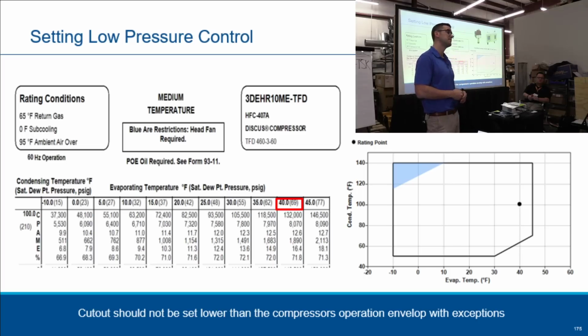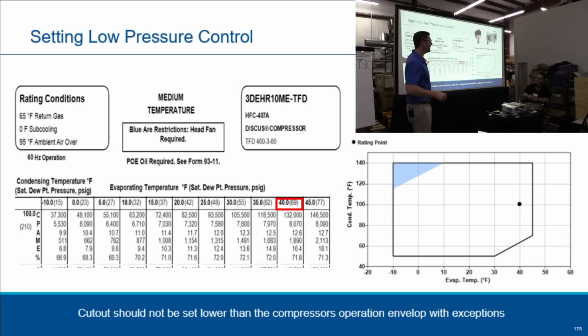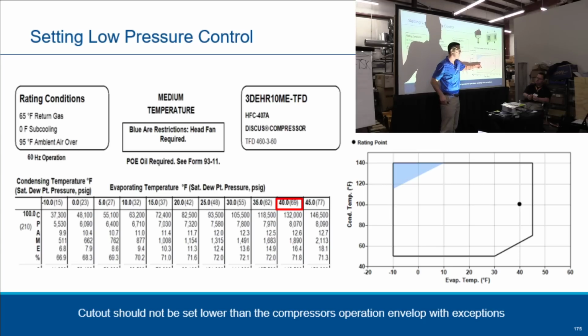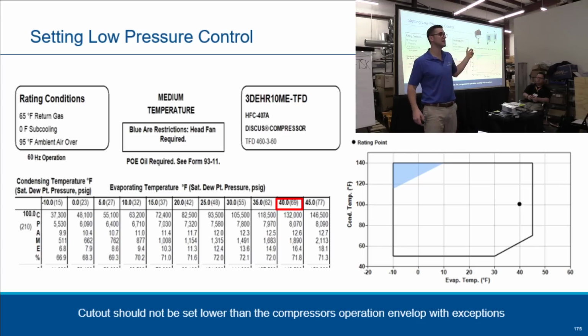Okay. So does everybody kind of understand this? If you set it, instead of all the way down to here, only right to here, just say 0, you're doing less work on that compressor, right? So a good mechanic won't set it right to the lowest. They'll know when that evaporator has all the refrigerant out of it and it shuts off for the right amount of time until that system starts back up again. Okay.